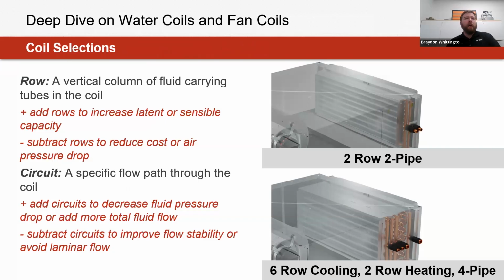Rows, again, allow for a higher amount of latent or sensible capacity provided from the coil, just at an additional amount of pressure drop that's going to be induced. I know we mentioned this earlier in the presentation, but for fan and blower coils, the typical row count is going to be up to 8 rows as a maximum of what we would see in terms of a cooling coil or heating coil that can be paired with this product. And then circuitry, the number of fluid paths going through the coil itself. And the fact that we're dealing with bigger coils, I think Jonathan mentioned that earlier, means a little bit more customizability in terms of what circuitry we can play with when looking at fan and blower coils.